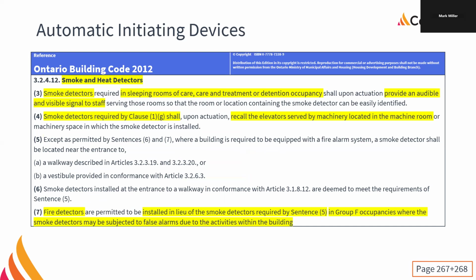The things we have to do in addition to just throwing in smoke detectors, though, it gets a little bit more complicated. Well, zoning is pretty vague, right? Oh, there's a fire in this wing of the hospital on this floor. Well, that's good for the firefighters. That's not really good for the people in the building, right? Because, well, if they're in the hospital, they might not be able to get out of bed. And if they're in like a detention occupancy, they're not allowed out of the room. So we need to know exactly where the smoke detector is activated.